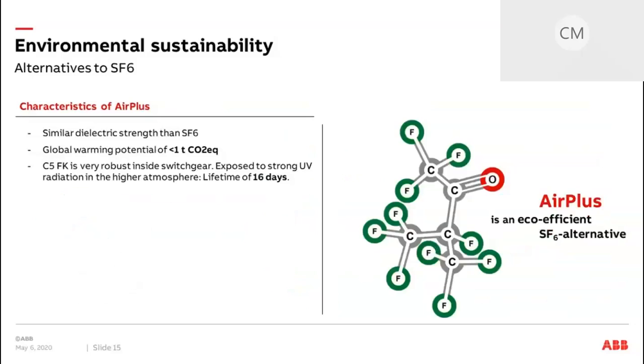But, and this is the major difference, the global warming potential of AirPlus is only 1 ton of CO2 equivalent. So it's comparable with air. That's why we call it AirPlus. It's very robust inside the switchgear, but once exposed to strong UV radiation in the higher atmosphere, it will decompose, so it only has a lifetime of 16 days.